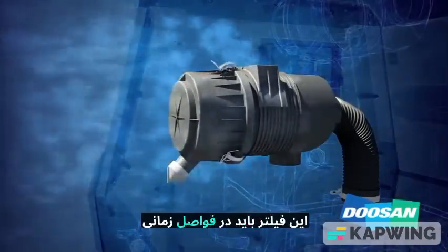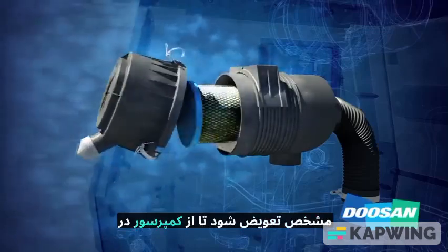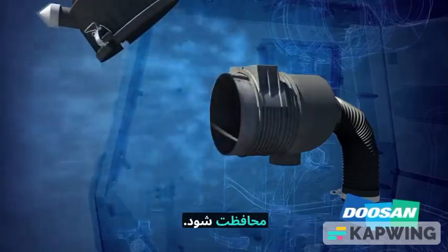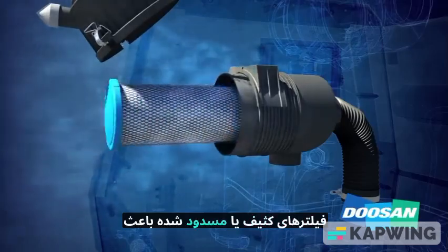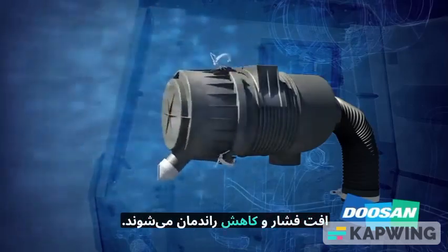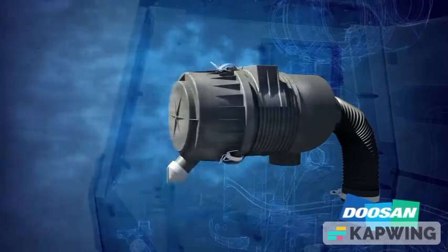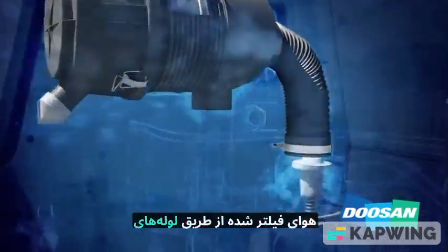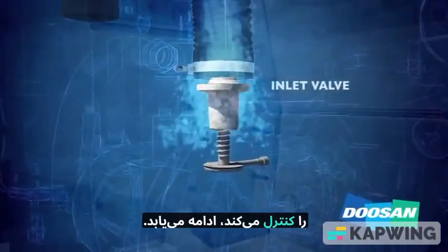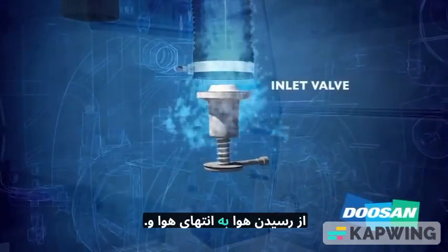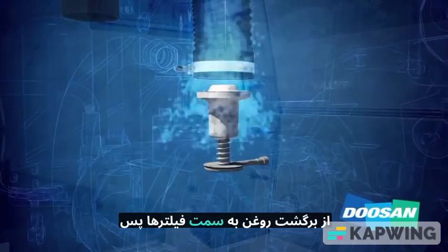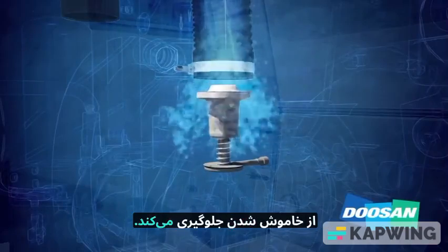This filter should be replaced at timely intervals to ensure the compressor is protected from unwanted contaminants. Dirty or restricted filters cause pressure drops and reduced efficiency. Filtered air continues through sealed piping to an inlet valve that controls the volume of air reaching the air end and prevents oil from reversing towards filters after shutdown.